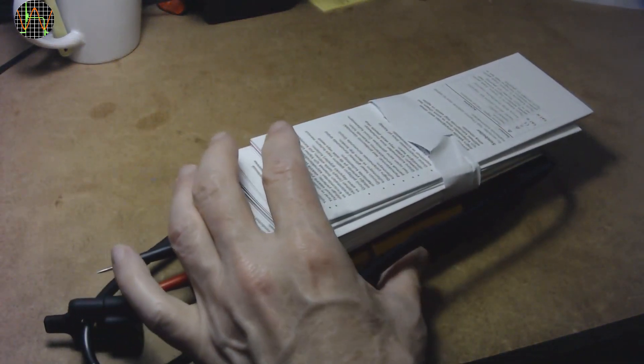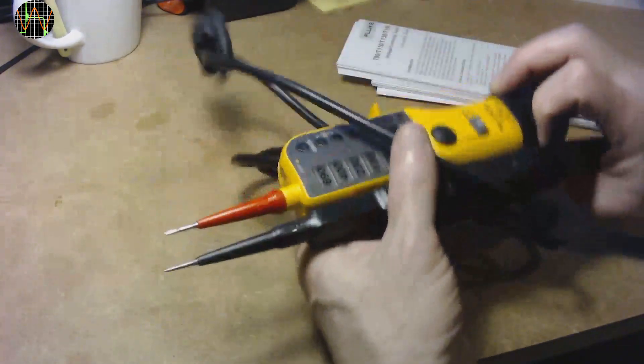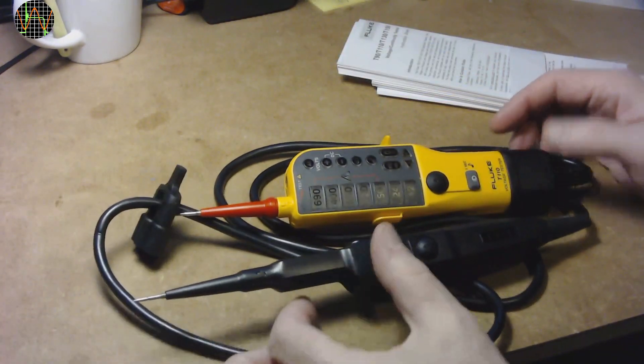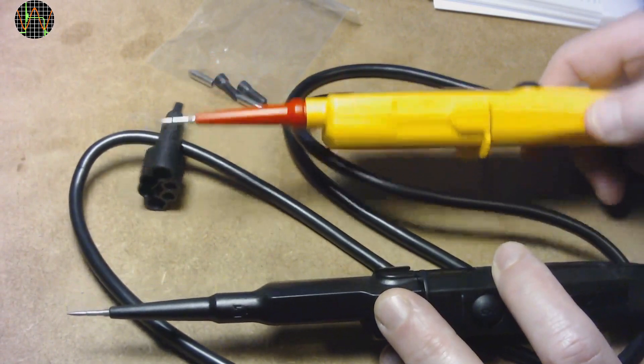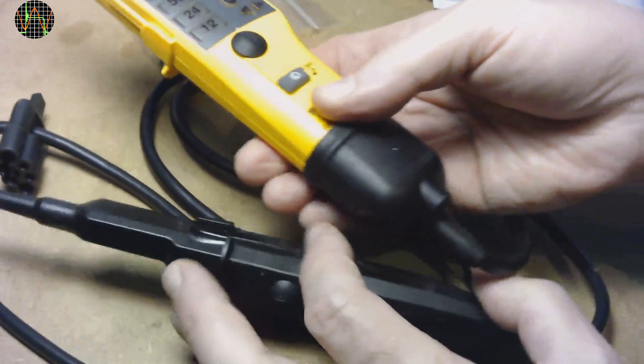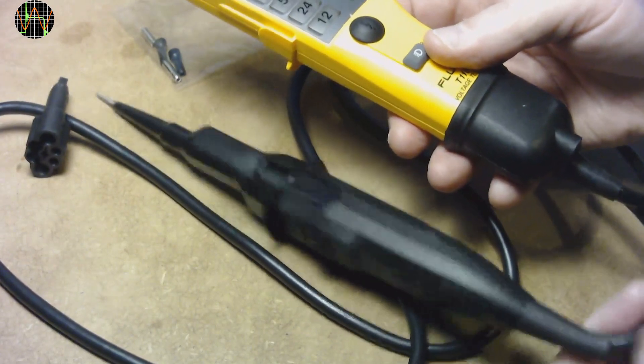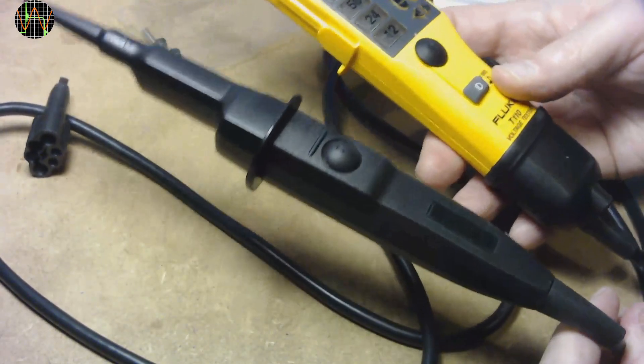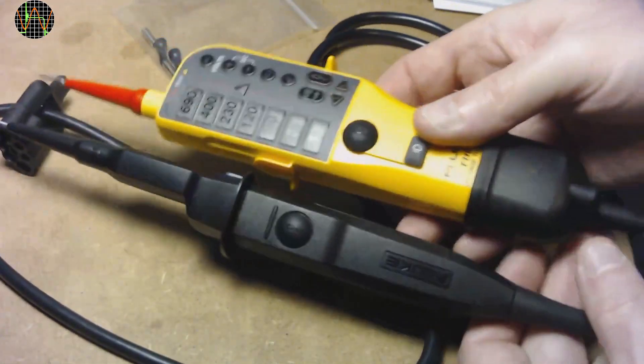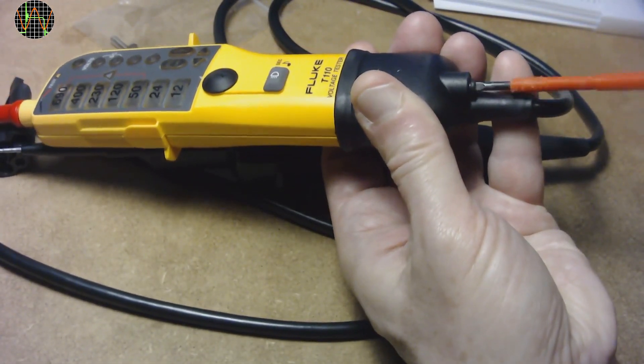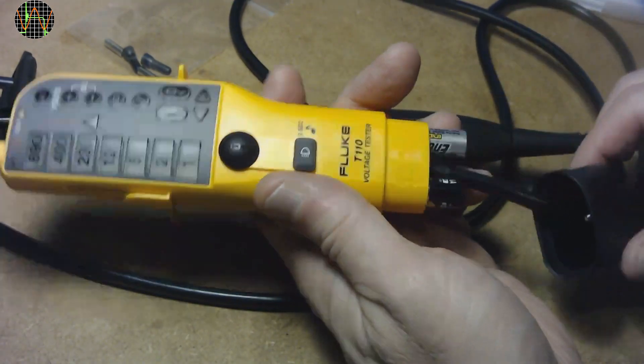It comes with instructions in like 16 different languages. And here is the little pack with additional probe tips and shrouds. It looks exactly the same as the old model, which according to Fluke has an issue with the strain relief of the connecting cable, which can cause the tester to intermittently fail detection of dangerous voltages. Also, Fluke detected that the cable itself may fail under repeated bending stress. I can't detect any differences. Let's open the battery compartment and check the cable inlet. Hey, they even included a set of new batteries. Very nice.